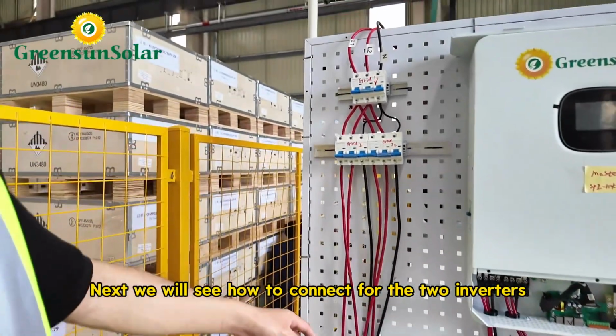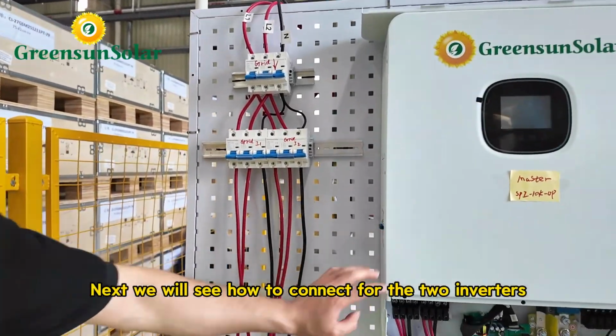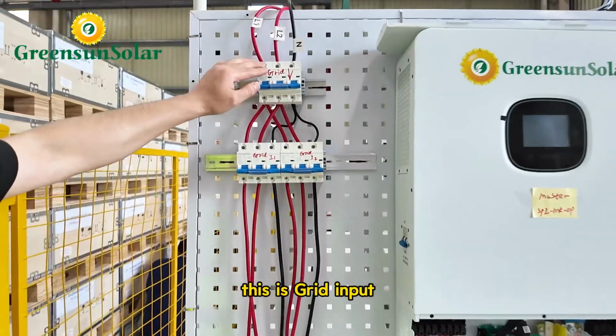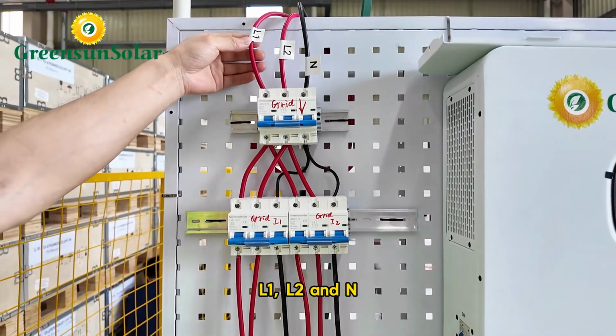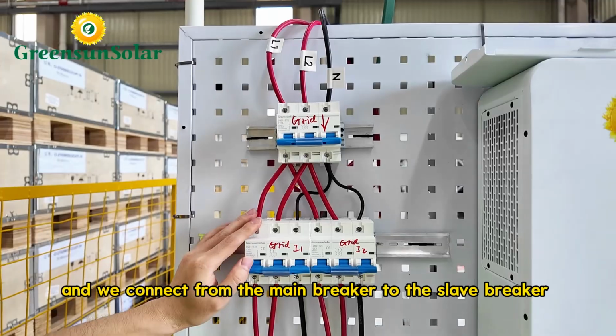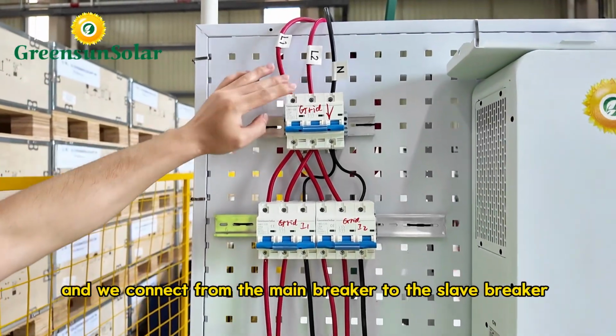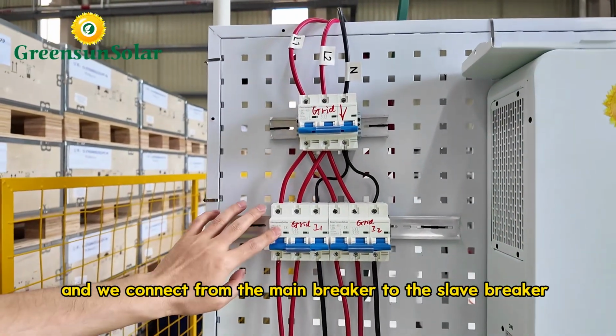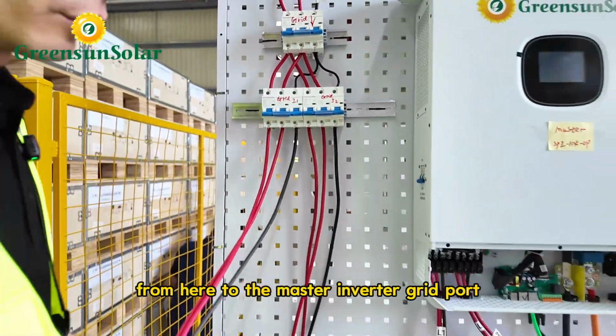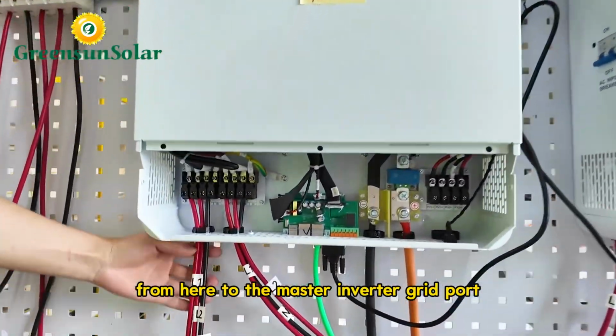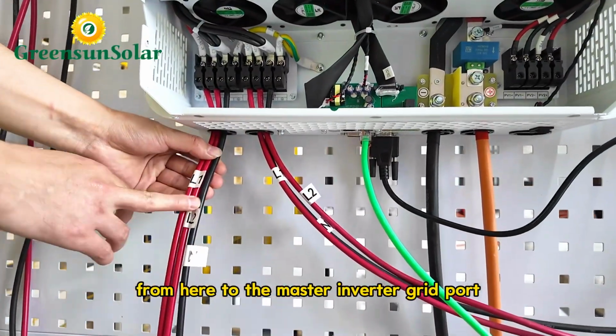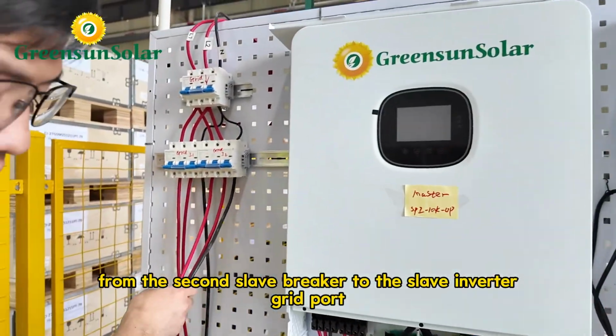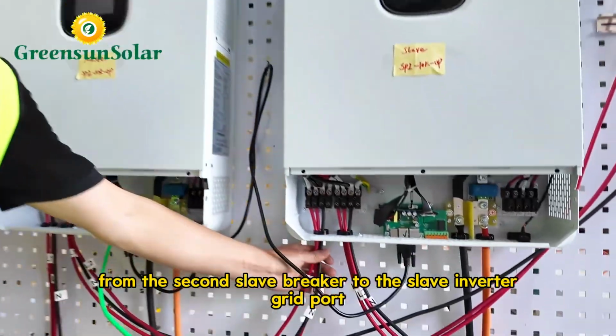Next, we will see how it connects for the 2 inverters. This is the grid input: line 1, line 2, and neutral. We connect from the main breaker to the sub breaker, from here to the master inverter grid port, and from the second sub breaker to the slave inverter grid port.